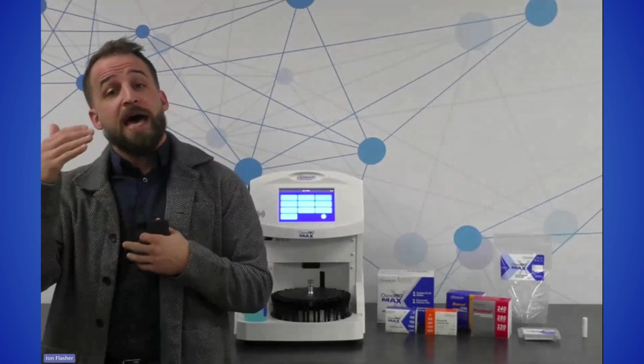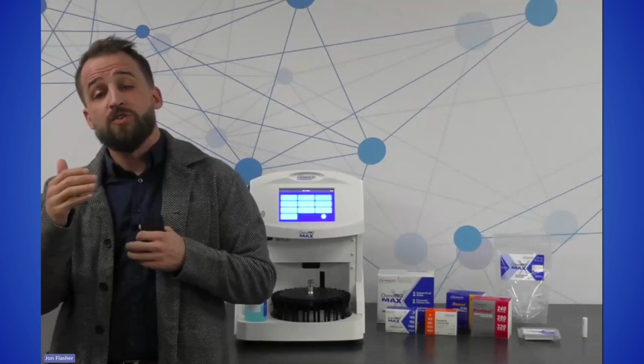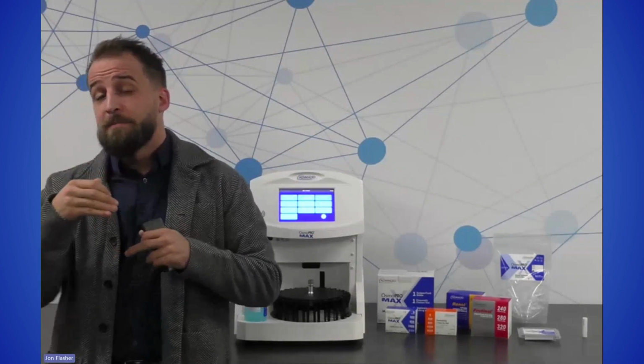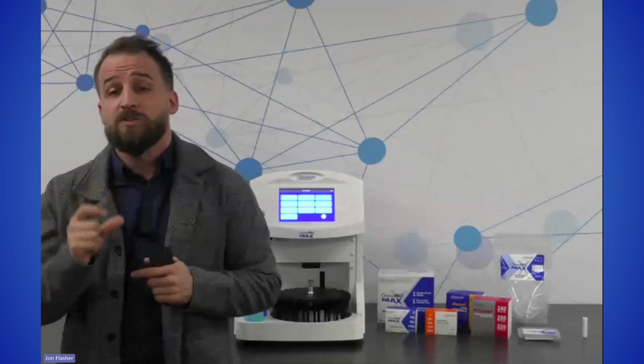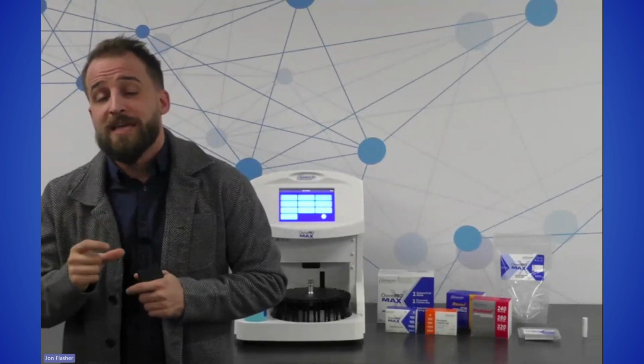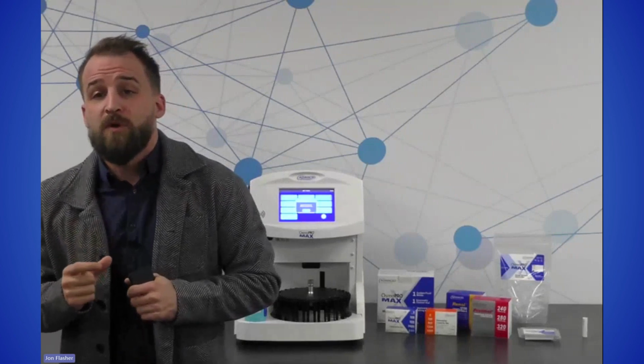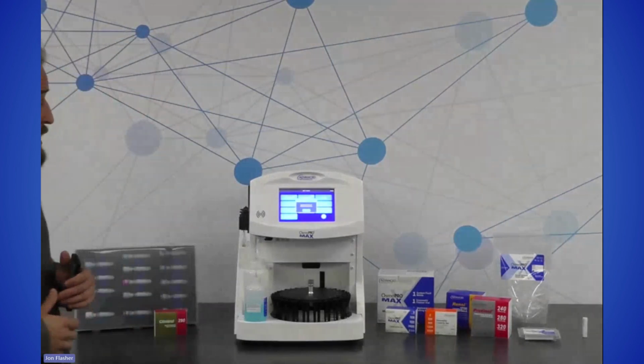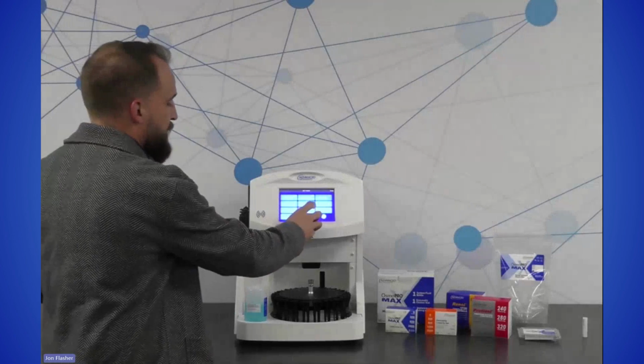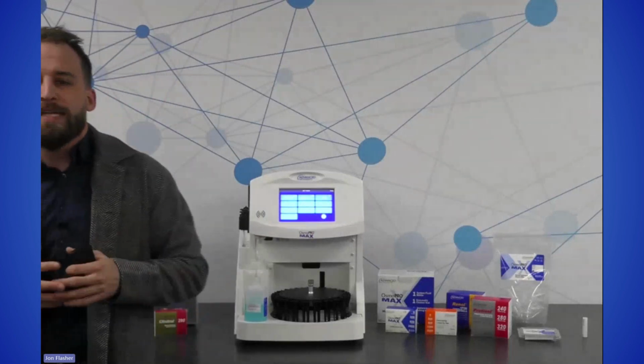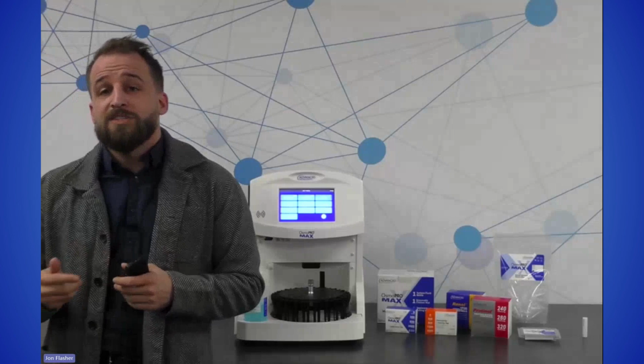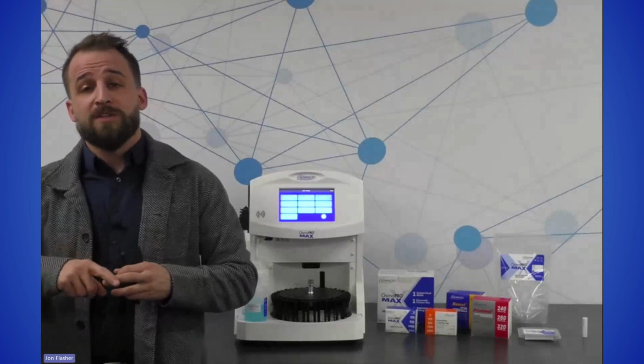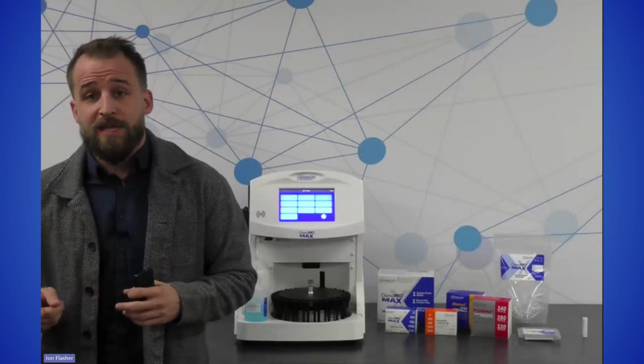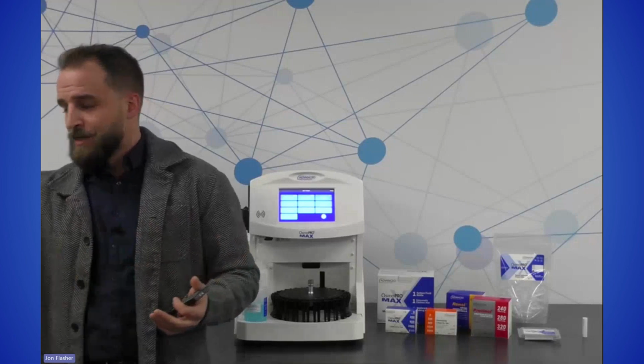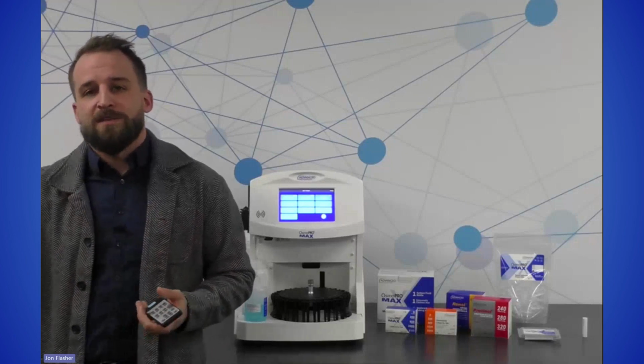If it's outside of plus or minus 2 milliosmoles and within plus or minus 6 milliosmoles of the baseline Clinitrol 290 result that you established at the time of calibration, the instrument will perform what's called a single point adjustment, which is kind of likened to what you would expect on an instrument like a blood gas analyzer. So if it's outside of that range, it'll automatically re-baseline your 290 result, prompt you to run another 290 sample, and then once that result passes, you're free to continue testing throughout the rest of the day.